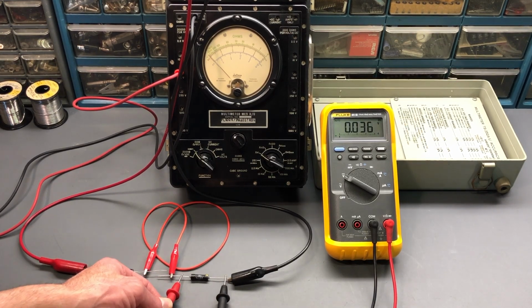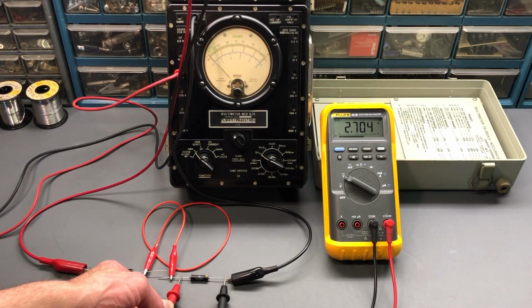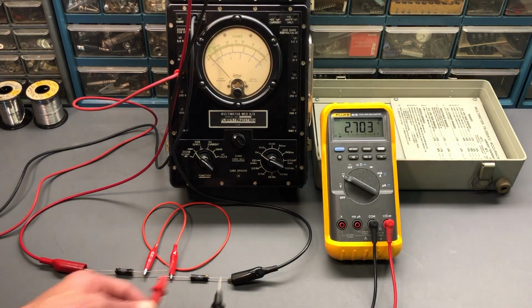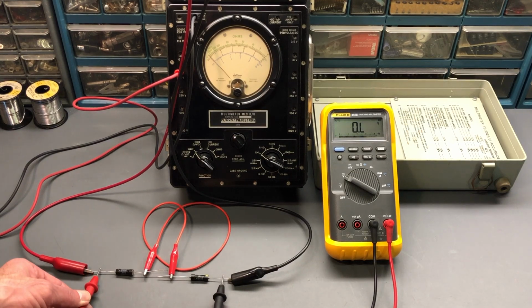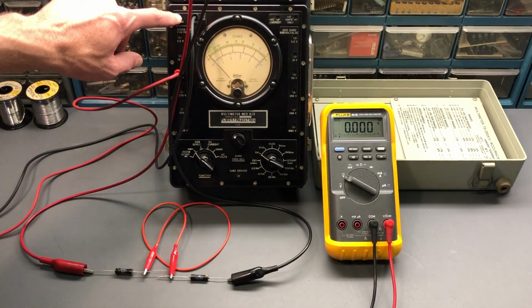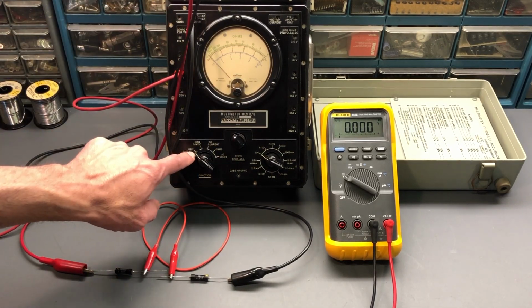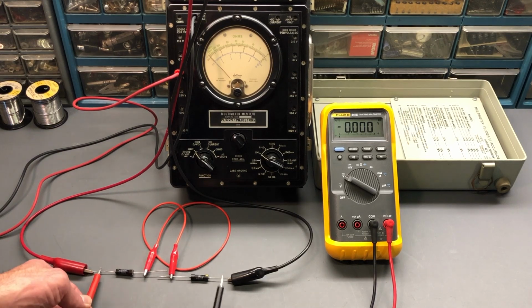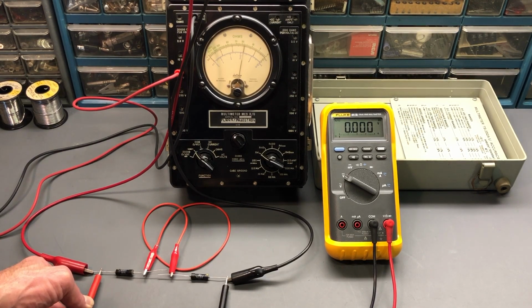And we see it's exactly 30.00. This resistor, 27.16, and over here we have 2.704. All right. So again, going back to that total, we have exactly 30. So let's take a look at that total voltage on this meter. So we're on the 20,000 ohms per volt direct reading. So the positive to the positive side, negative to negative side over here. And we do see it's exactly right on 30. So that looks very good.